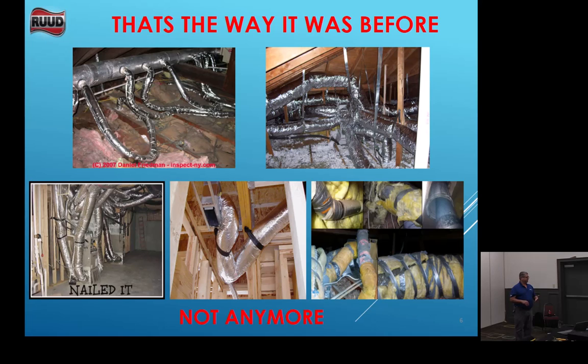Probably not, okay? Because just like the insulation in your home, they tell you after 20, 30 years that insulation settles. The R value is not what it used to be when it was put in brand new, right? It's the same way with this. That R value might have been R2 or R4 30 years ago, and now it's R nothing. And that's what you see with a lot of change outs. That old wrapped insulation looks good, but the R value is just not there anymore.